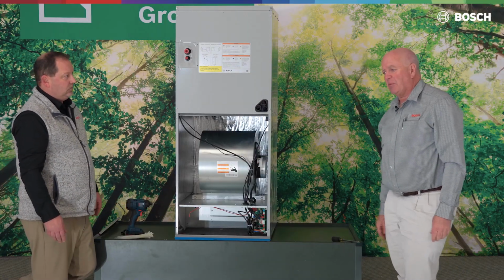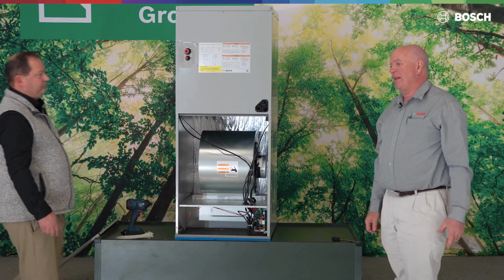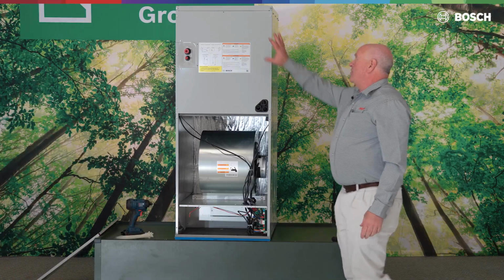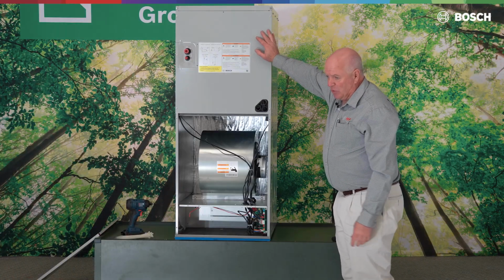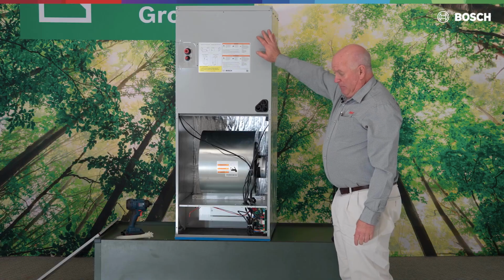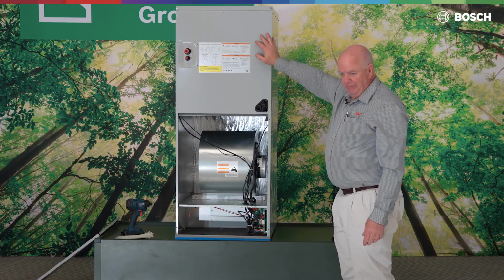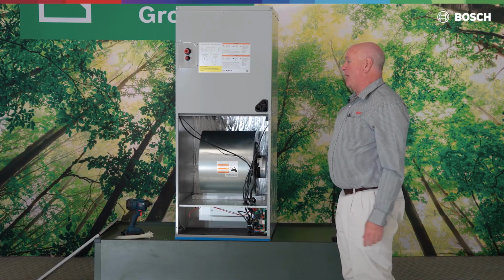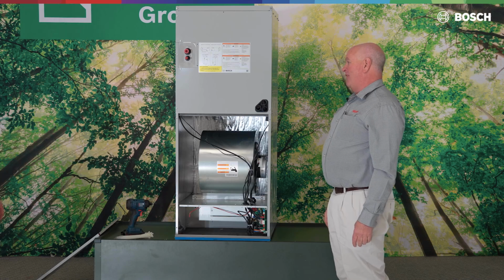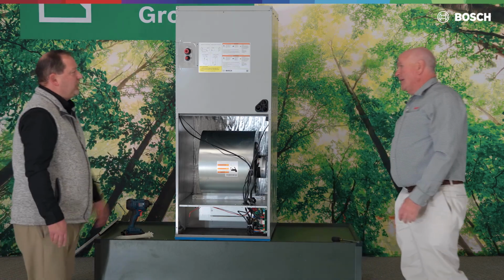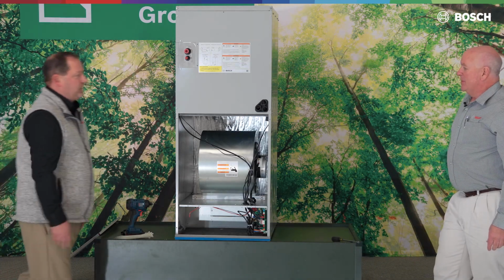When we go to defrost, we put that unit back into AC mode. When it's running in AC mode, the fan continues to run. It runs on low speed during that defrost cycle, but it will blow cool air into the home. Typically 50, 55 degree air possibly coming out of the unit for up to 5.5 minutes. So we're probably looking at 5.5 minutes. And why do we have such a short defrost cycle?